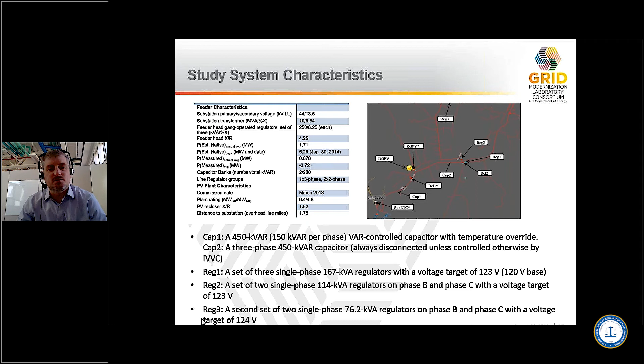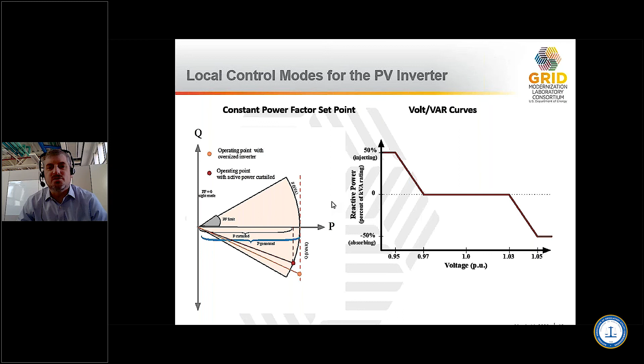So the control modes for the PV inverters. I mentioned there's a large PV system, actually more than one, but the main case is this 5 megawatt large PV system. There are a lot of things those PV inverters can do, from a control standpoint. They can do constant power factor set point control, meaning you just say operate at 0.95 lagging all the time. There are also volt-var curves, meaning the reactive power output the PV inverter supplies depends on the voltage. These are all things meant to try to mitigate the impacts of that large PV system, if requested to do so. We'll see how that plays out here in just a minute.